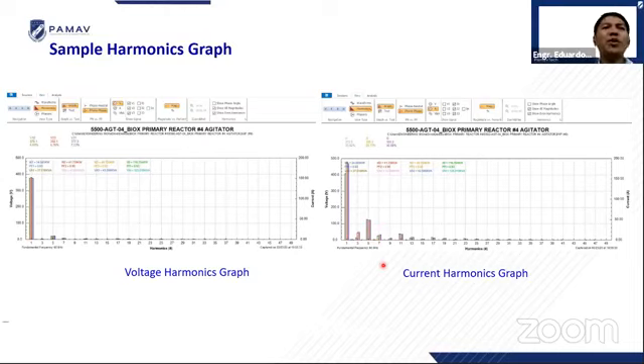But sometimes we cannot analyze by total harmonic distortion. We need to analyze the individual current, not in percent, but in current, okay? Because sometimes if you measure, you have a very high total harmonic distortion, but your current is so small, 0.5 ampere or 1 ampere. So it's better to look at the current harmonics like this one.